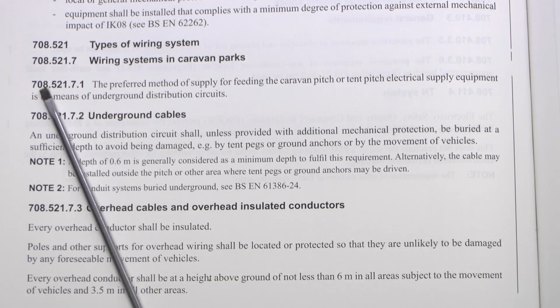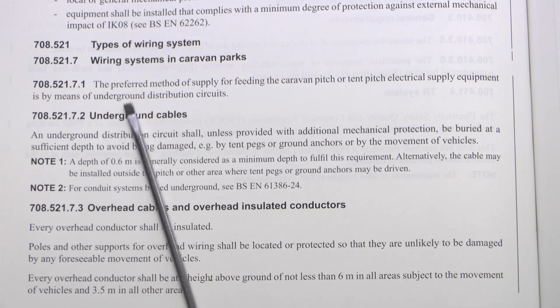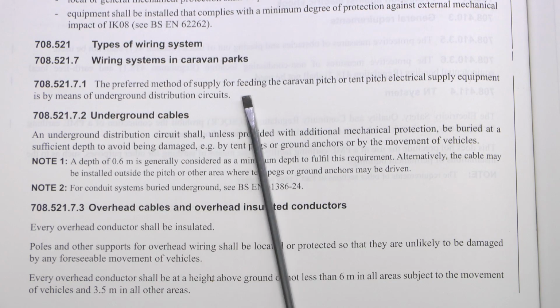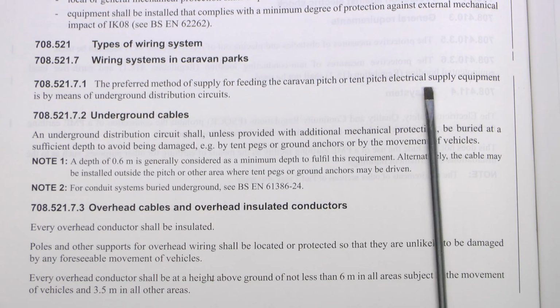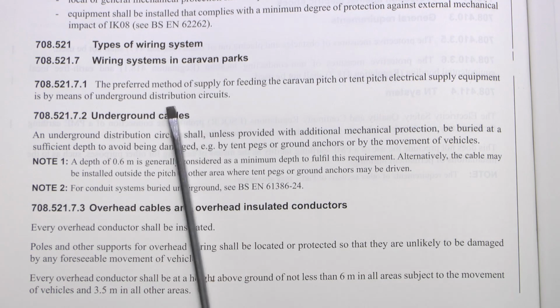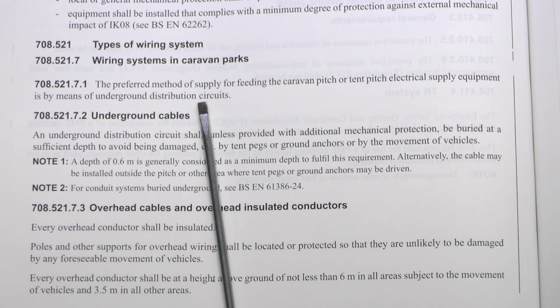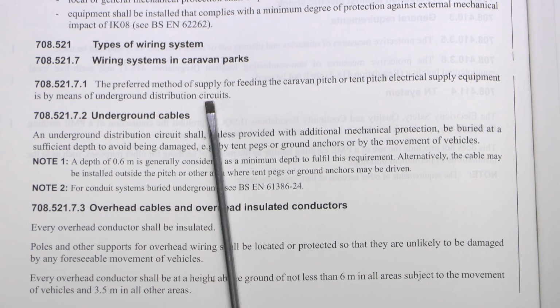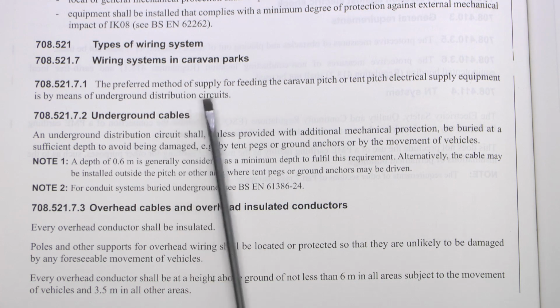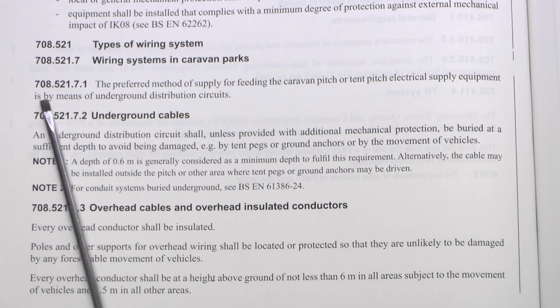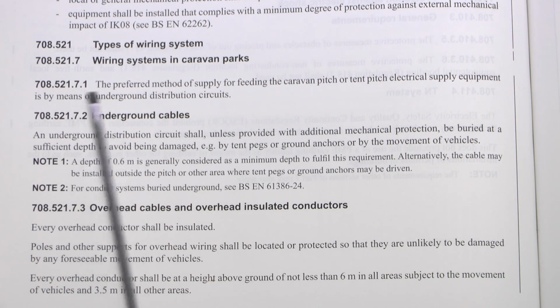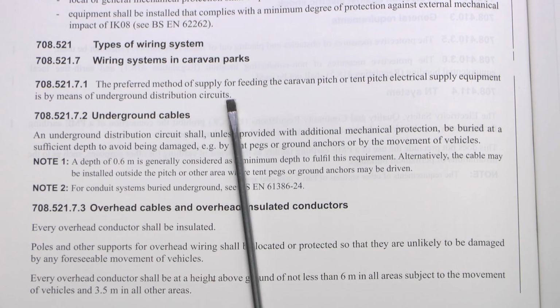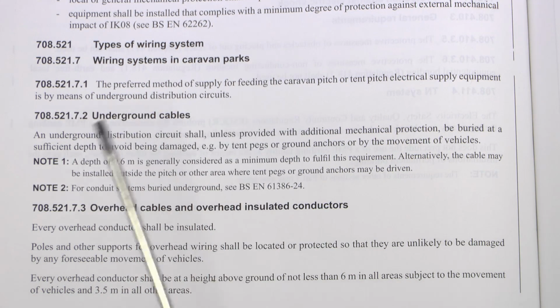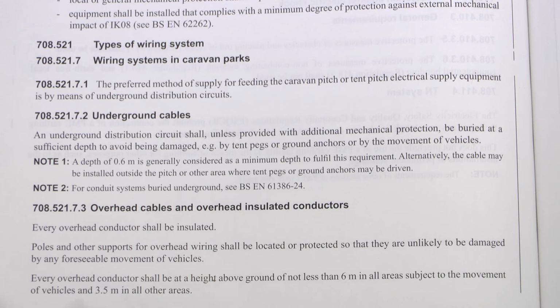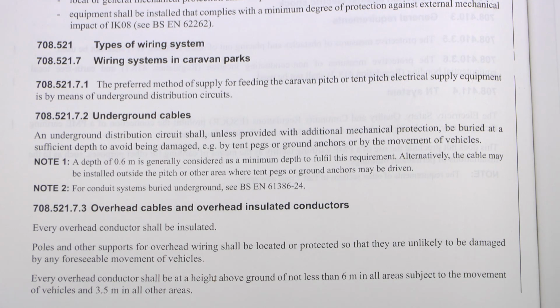And an amendment here which is 708.521.7.1. And we've now got the preferred method of supply for feeding the caravan pitch or tent pitch electrical supply equipment is by means of underground distribution circuits. Now previously the thing actually stated that underground or overhead was suitable, and then there was a note which said that underground was preferred. So pretty much the same thing, except now I've got an actual numbered regulation which states that underground is preferred. And again, that's pretty much common sense, because overhead obviously is a certain height, and there's likely to be large vehicles moving around there fairly often.